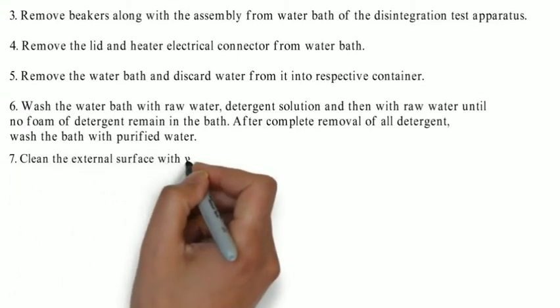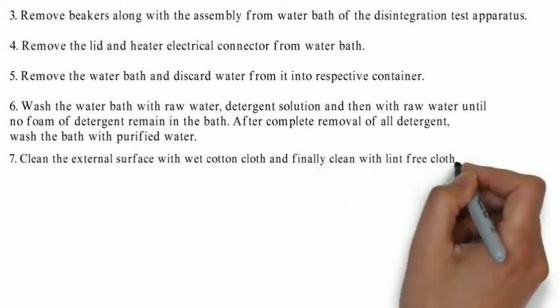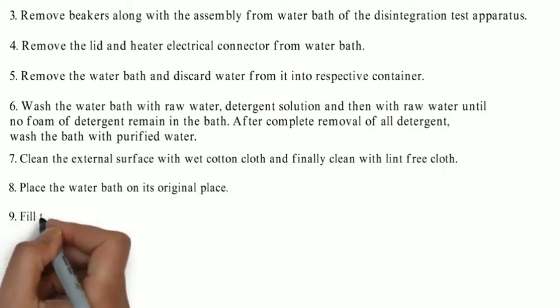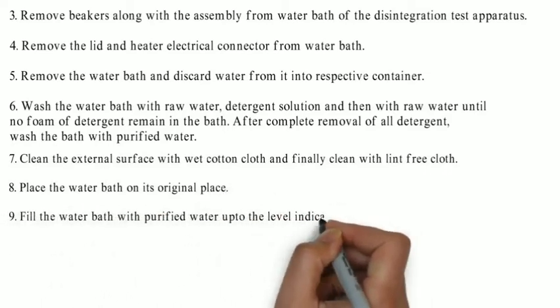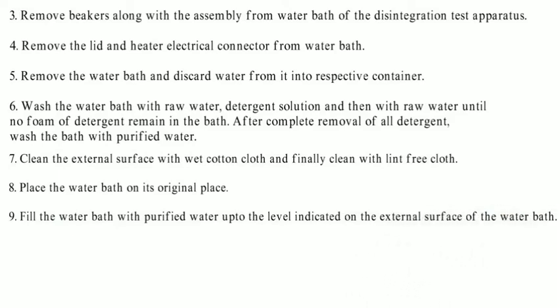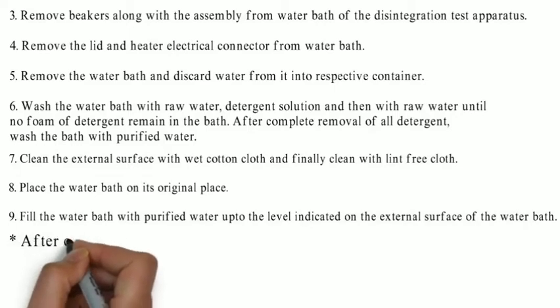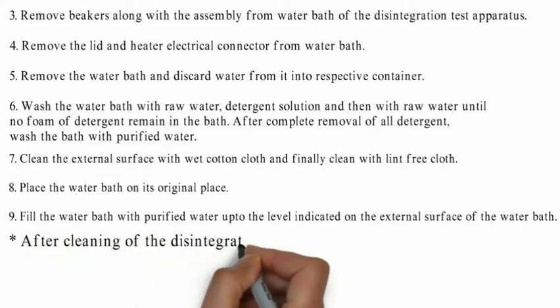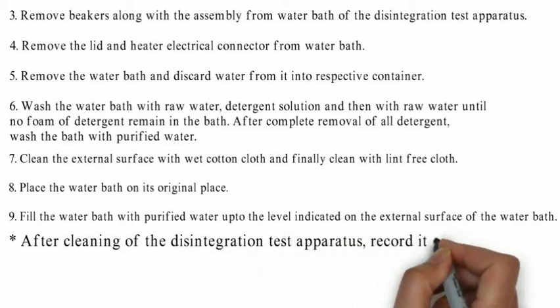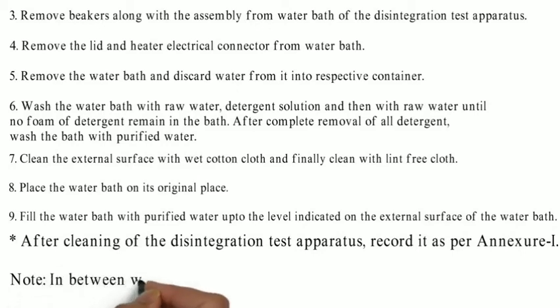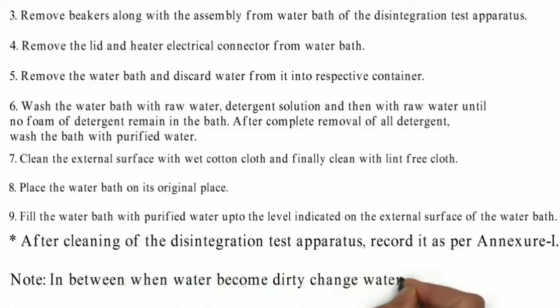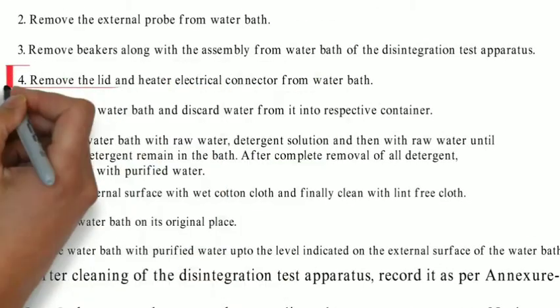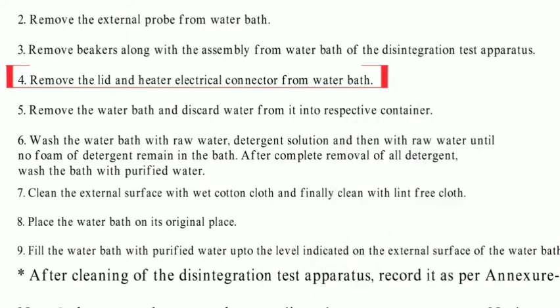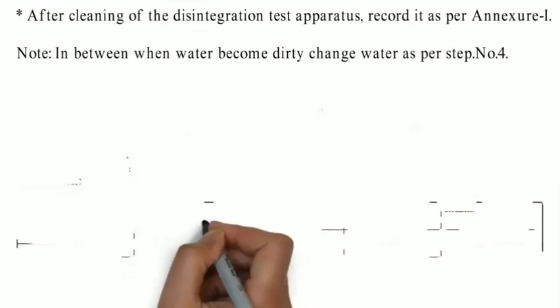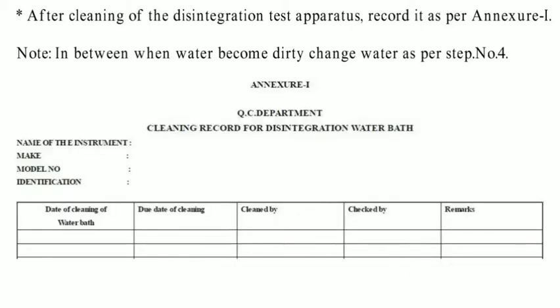Clean the external surface with a wet cotton cloth and finally with a lint-free cloth. Then place the water bath in its original place. Fill the water bath with purified water up to the level indicated on the external surface of the water bath. After cleaning the disintegration test apparatus, record it as per Annexure 1. What is Annexure 1? You will get it after some time. Okay, note one point in between: when water becomes dirty, change water as per step number 4. What was step number 4? Here you can see: remove the lid and heater electrical connector from the water bath. This is Annexure 1, so according to Annexure 1, you have to put your records into it.